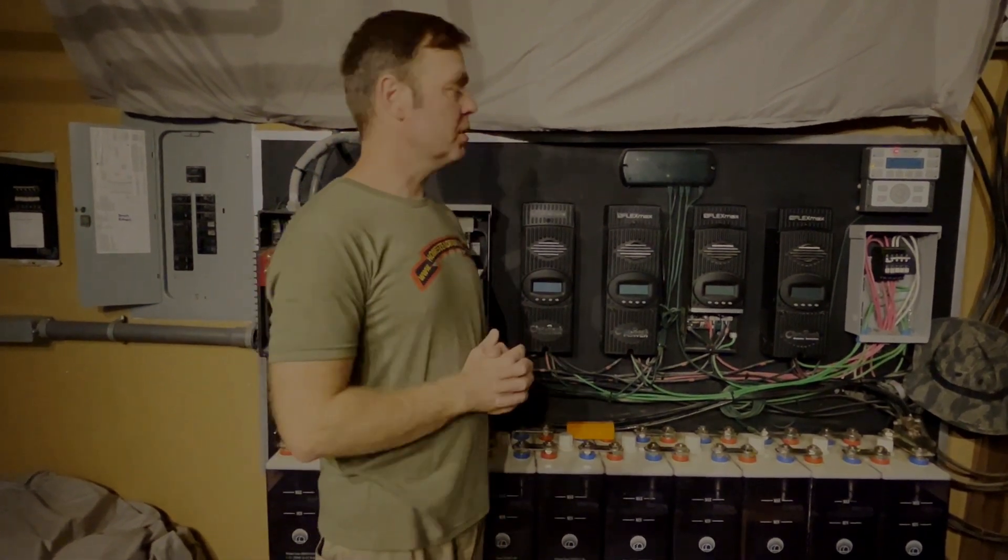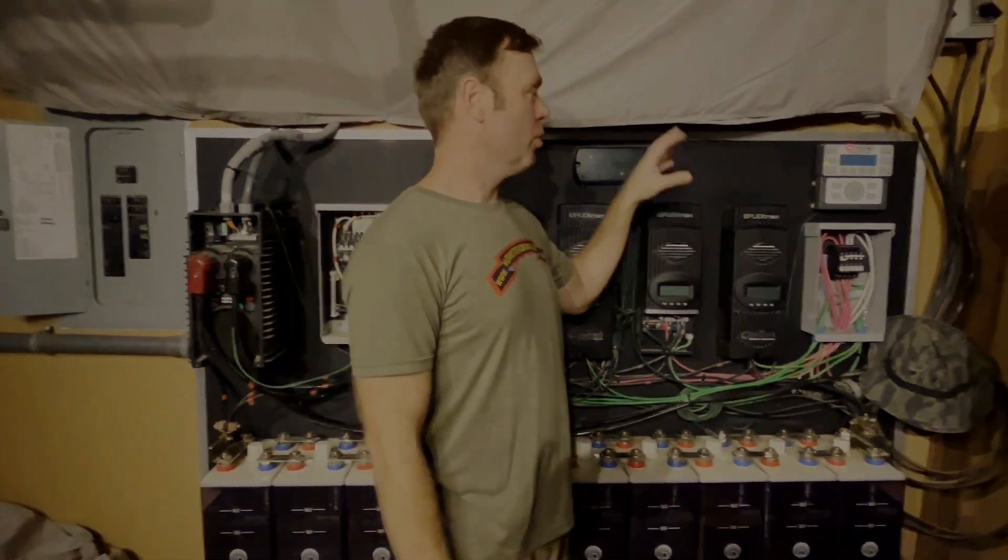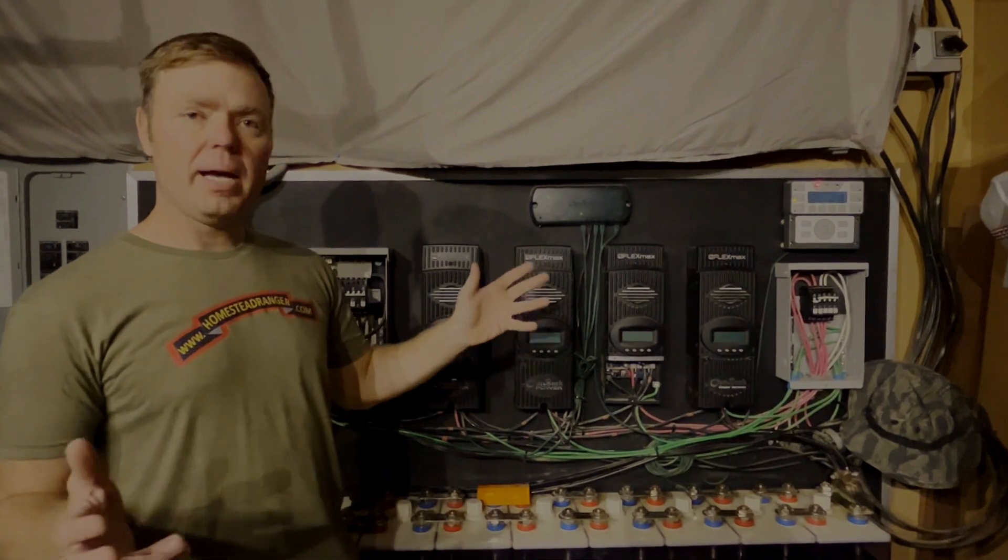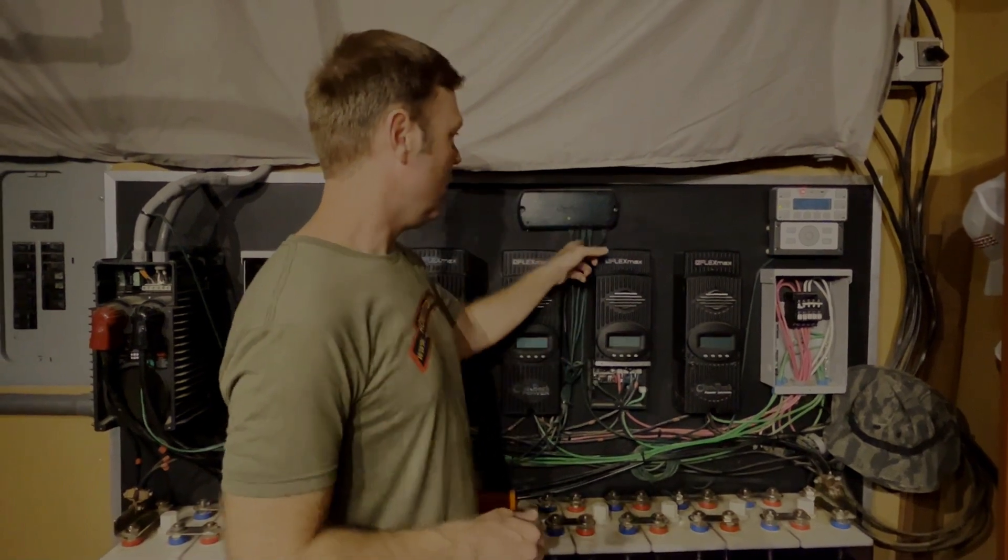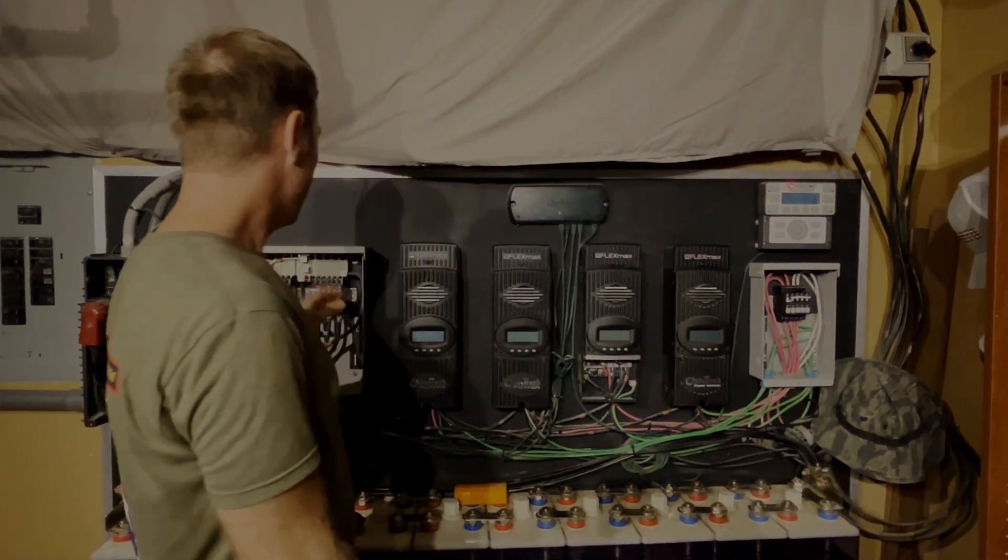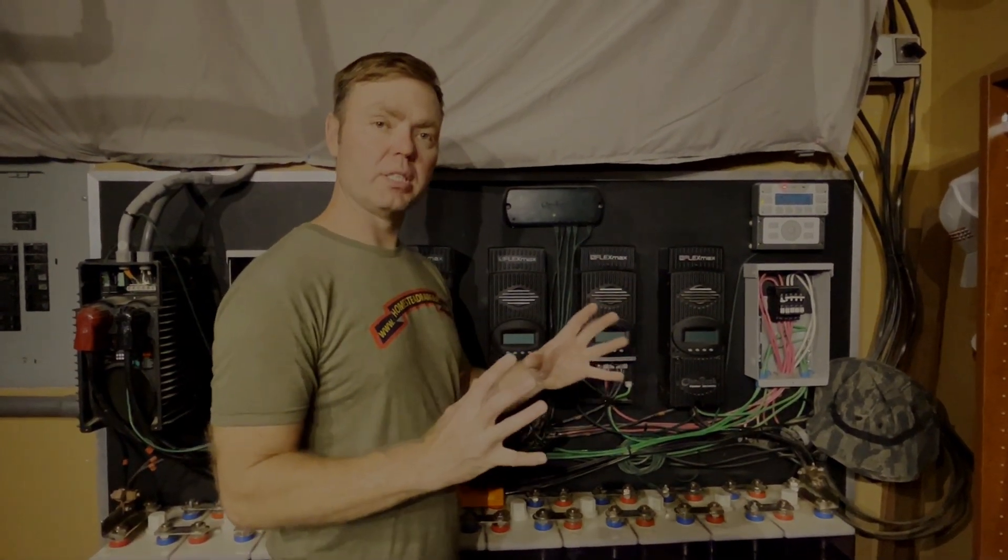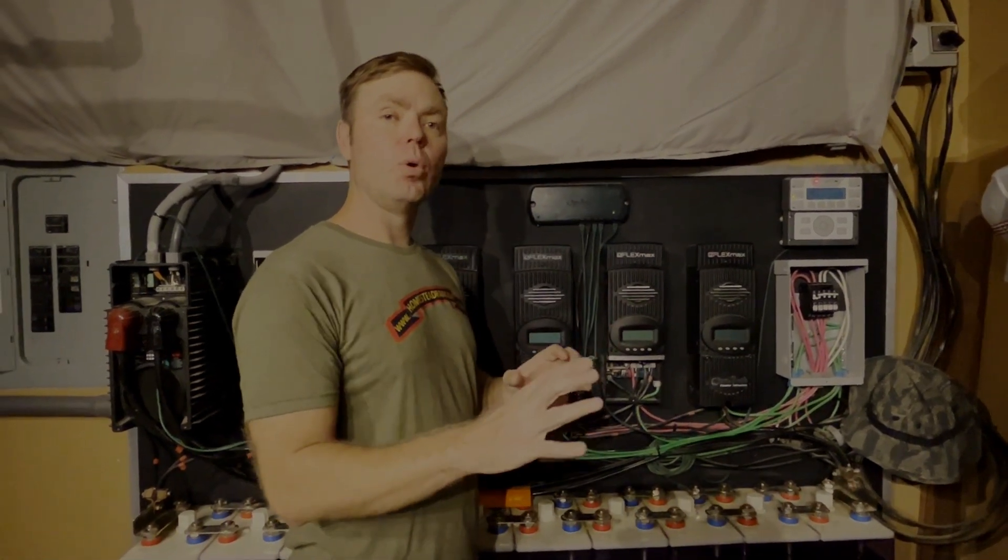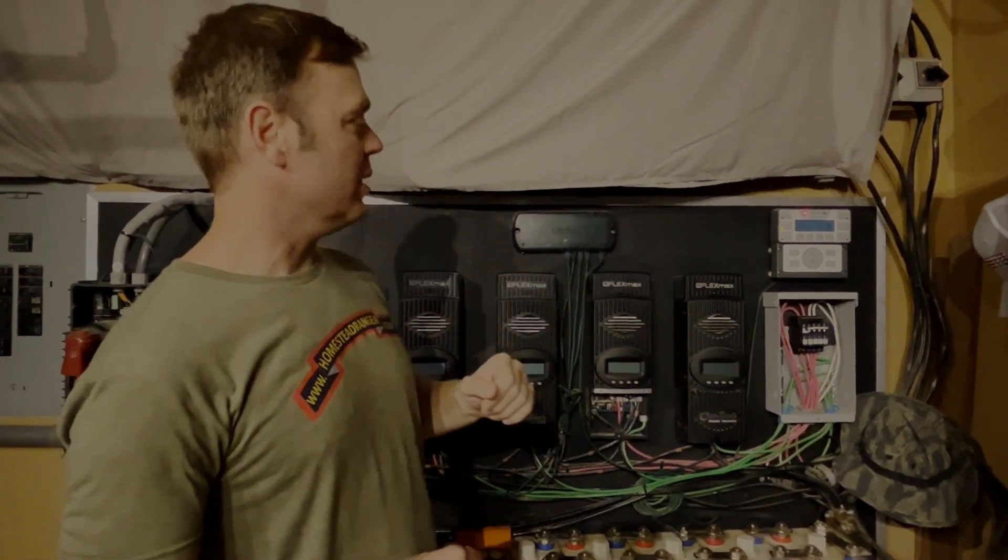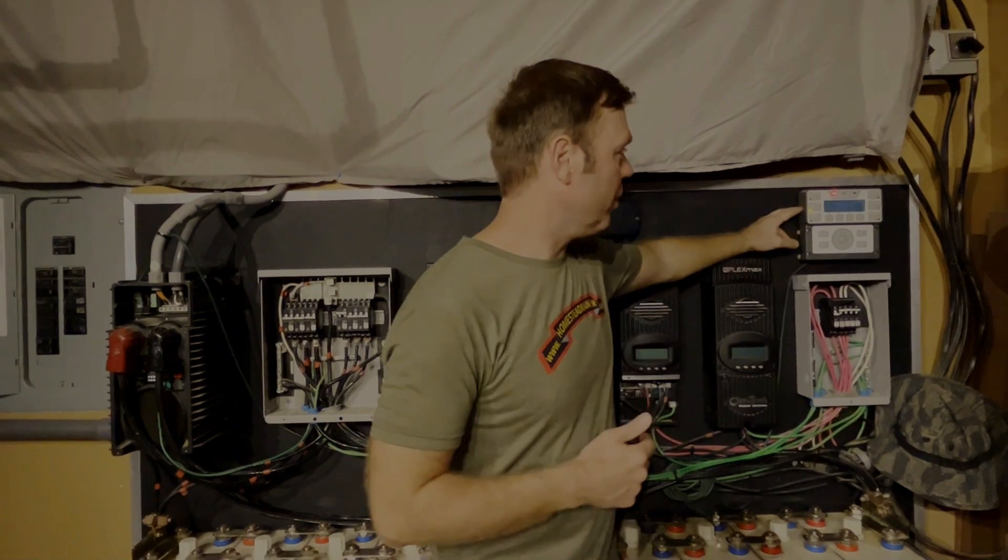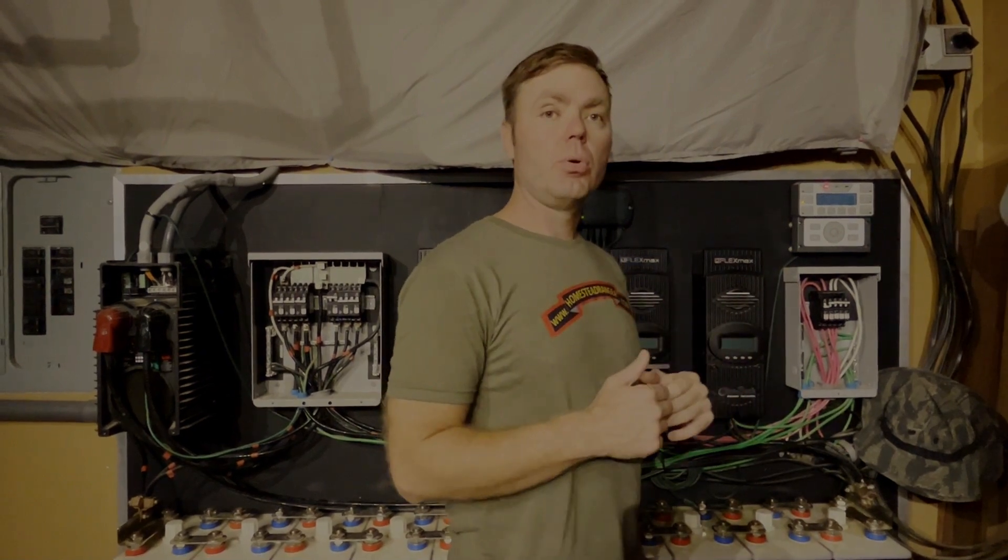There's one other thing left to talk about within this power center, and that is your hub and your mate. All my equipment here is Outback equipment, which I really like. You have a hub, and your hub has a LAN cable that goes to each charge controller and goes to your inverter. It communicates between them so that your charge controllers can work together, and they can give the proper amount of voltage and amperage to your batteries to charge them at the proper rate. Your hub also has a LAN cable that goes over here to your mate. This is a mate 3, and the mate 3 allows you to set all of your charging parameters for all of your charge controllers at the same time.